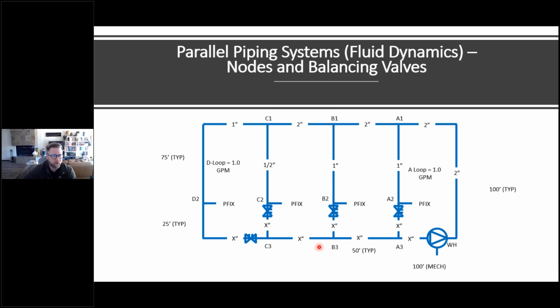Now, the one trick is when we're talking about doing the parallel pipe system sizing, we don't know what the size is for all the hot water return segments here. It's not known. This is one of the things we're trying to figure out because it's based off the flow. So a good approach in this case would be to take an initial guess, right?